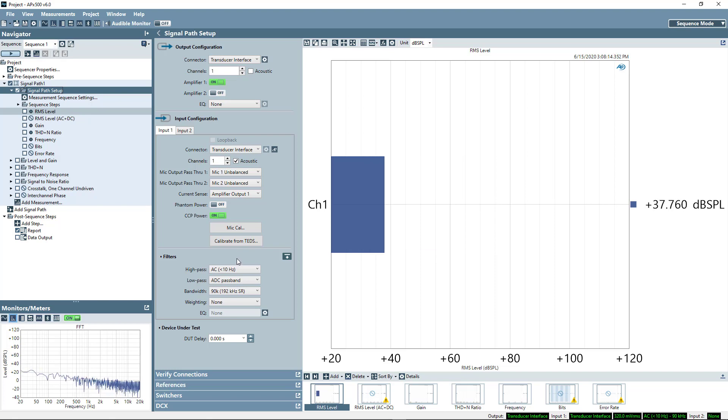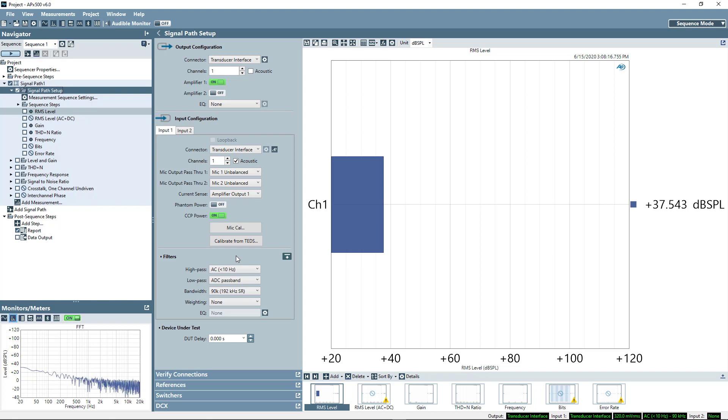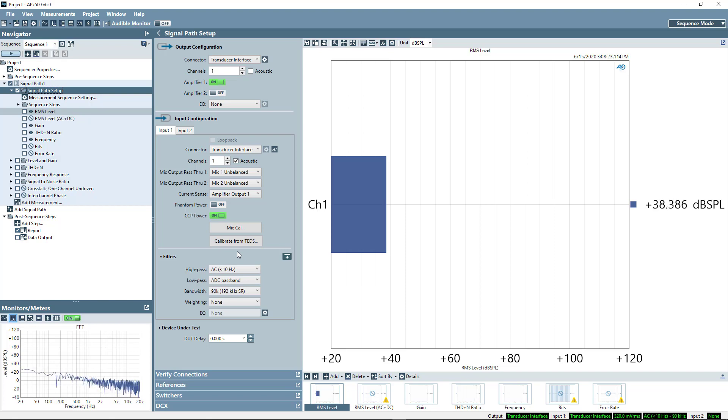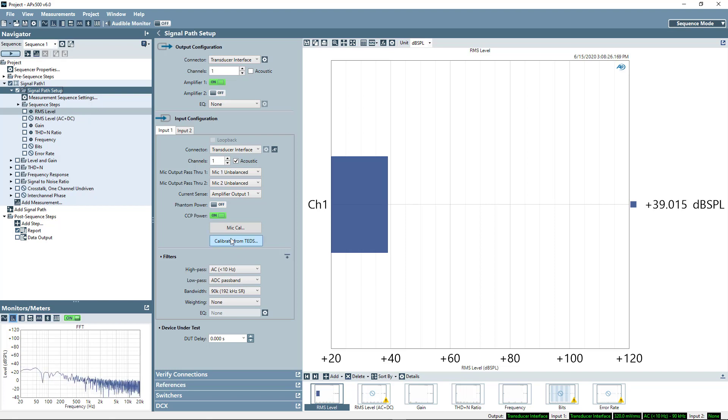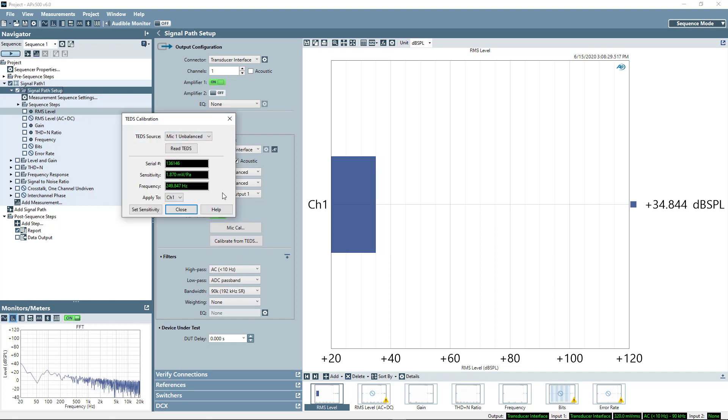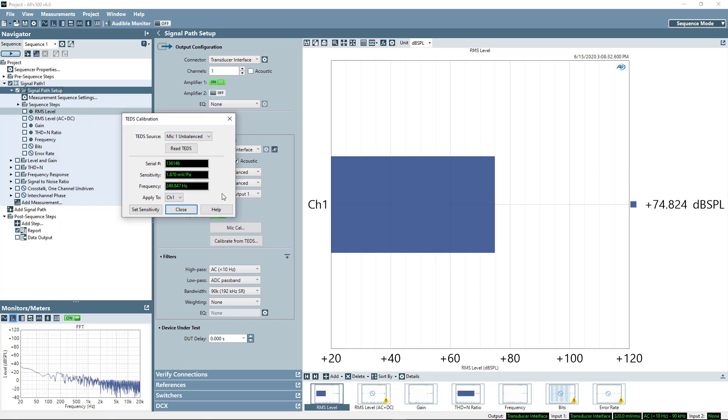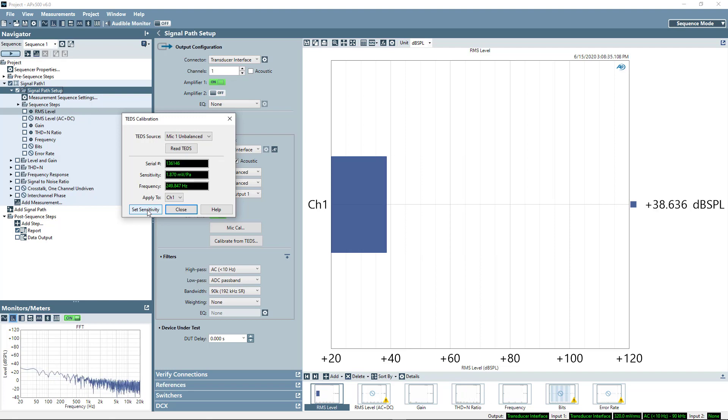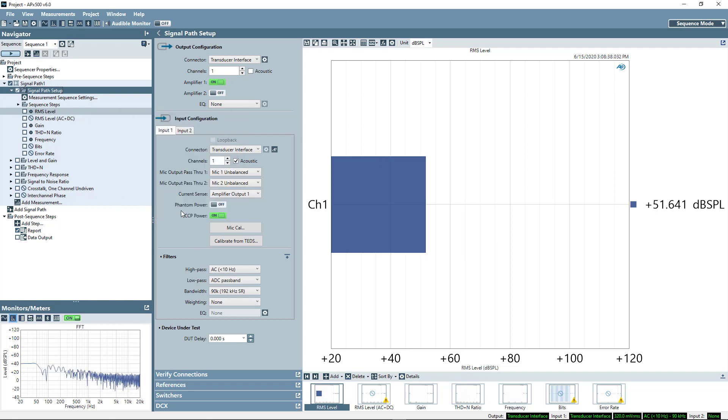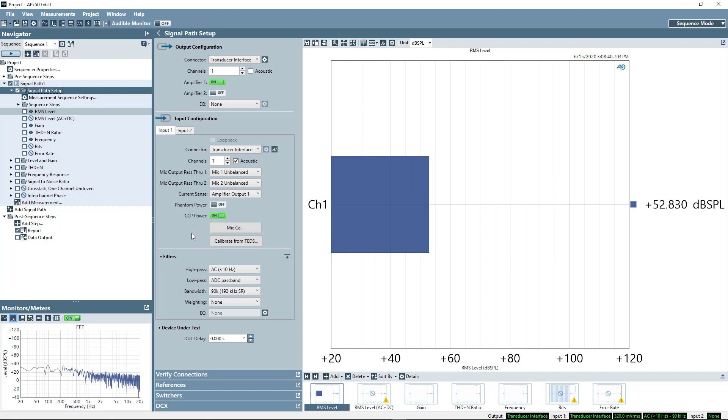Now I happen to be using a TEDS microphone, or a microphone with a transducer electronic data sheet, and so I can actually read the calibration information directly from the microphone using the calibrate from TEDS button. I'll select read TEDS data, and then I'll select set sensitivity. And quite conveniently, my microphone sensitivity is now set.